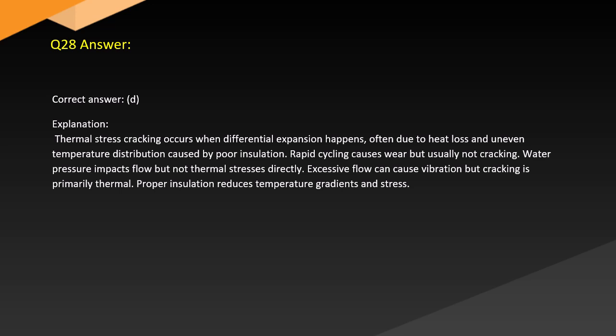Answer. Correct answer, D. Explanation. Thermal stress cracking occurs when differential expansion happens, often due to heat loss and uneven temperature distribution caused by poor insulation. Rapid cycling causes wear, but usually not cracking. Water pressure impacts flow, but not thermal stresses directly. Excessive flow can cause vibration, but cracking is primarily thermal. Proper insulation reduces temperature gradients and stress.